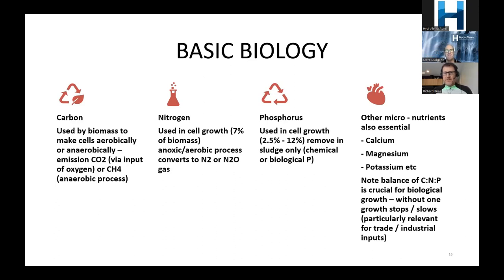With biological phosphorus removal you can find somewhere between 2.5% and about 12% phosphorus in your sludge or biosolids. Other things we might be missing include calcium, magnesium, and other micronutrients — relevant when you're treating waste from, say, a chocolate factory where micronutrients are missing, or an abattoir where you have lots of nitrogen but not much carbon. We want to balance our biology — balance our mass of nutrient flows into the plant so bugs can do their job.